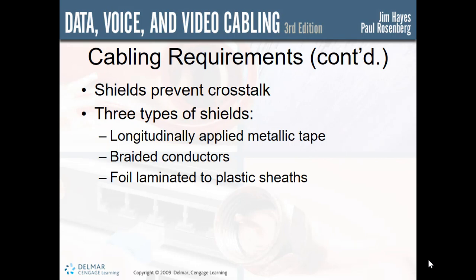Shielding is just like an insulator, and there are different types of shielding. One is an applied metallic tape, almost like an aluminum foil, which essentially has to be grounded. What that does is act as an antenna, absorb the electromagnetic field, and send it to the Earth's ground where it needs to be. Another, which we use on coax cables, is a braided shield, which is like metal around the whole entire wire or cable. Typically, it's around the PVC conductor that goes around it, and that is then grounded, and then the electromagnetic interference is sent there.